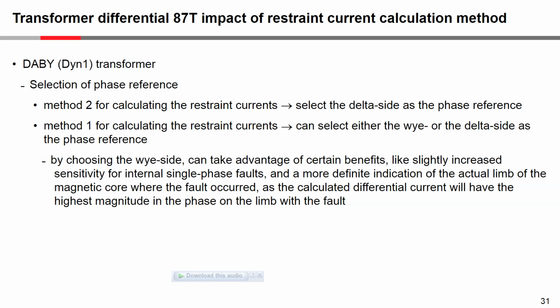was taken as the phase reference, then the maximum differential current would be calculated in one phase, and that differential current would be a little bit bigger, by that factor of 1.155, over the currents calculated if the delta side was taken as the phase reference. So by having slightly higher differential current calculated, you have slightly increased sensitivity. You get a more definite indication of the actual limb of the magnetic core where the fault occurred.